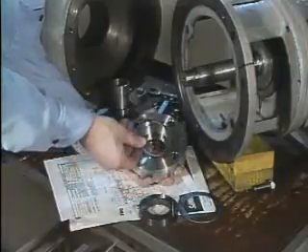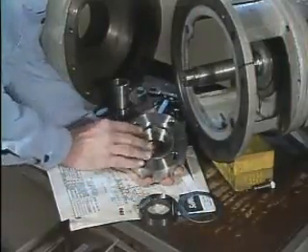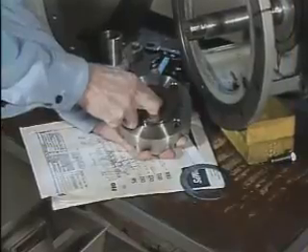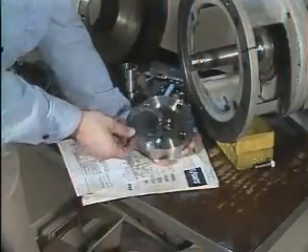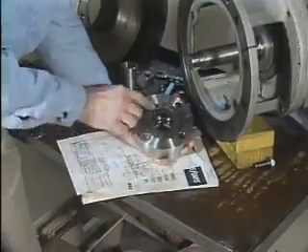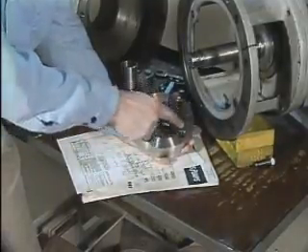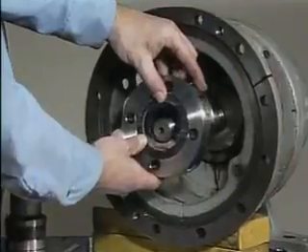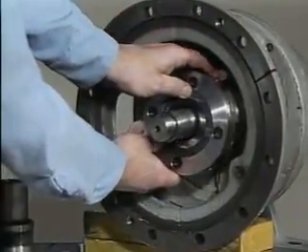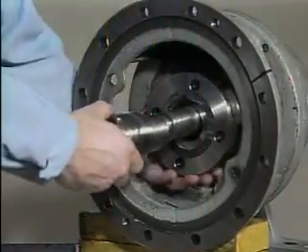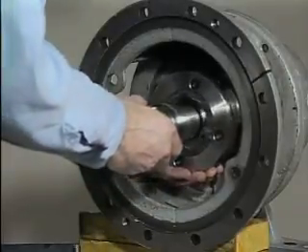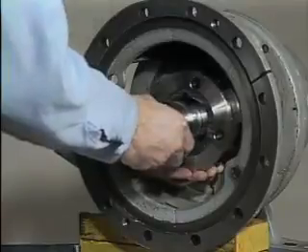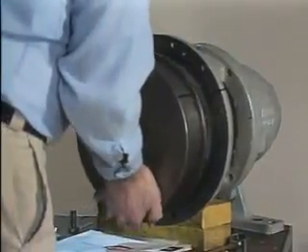Next, the gasket for the mating ring is inserted into the gland plate, along with the mating ring itself. Then the gasket that seals between the gland plate and the stuffing box is placed on the gland plate, and the gland plate is slid onto the shaft. Now the shaft sleeve is positioned on the shaft, and the collar set screws are tightened the rest of the way. Next, the pump back plate is installed.